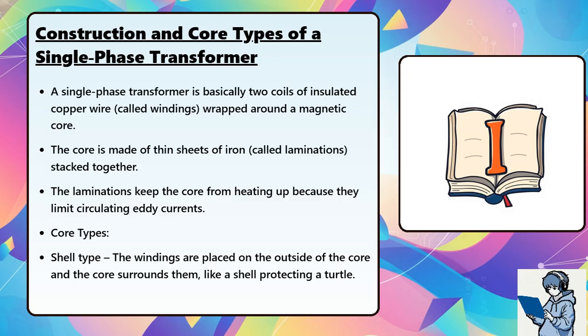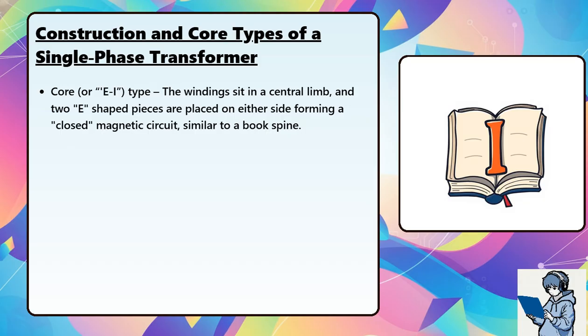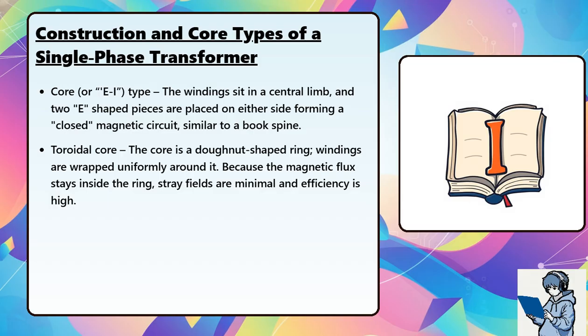Core types. Shell type: the windings are placed on the outside of the core, and the core surrounds them like a shell protecting a turtle. Core or EI type: the windings sit on a central limb, and two E-shaped pieces are placed on either side, forming a closed magnetic circuit similar to a book spine. Toroidal core: the core is a donut-shaped ring. Windings are wrapped uniformly around it. Because the magnetic flux stays inside the ring, stray fields are minimal, and efficiency is high.